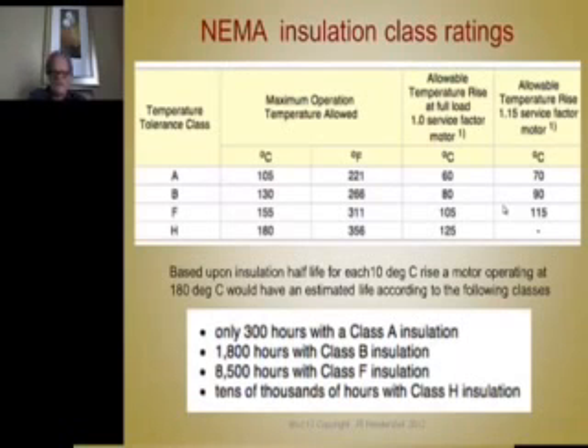Then there's a temperature rating system that's used around the world, and I guess it all started in America. It applies to transformers, to electric clutches and brakes. It applies to motors. It applies to all electric devices. Temperature rating classes of A, B, F, H. There's class C in there somewhere also, but it's not in this list. But here's the maximum allowable temperature for devices that are rated at these temperature classes.